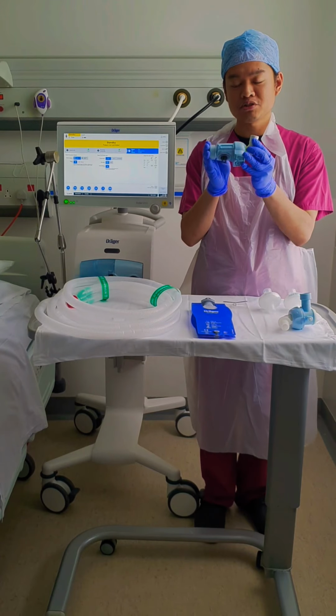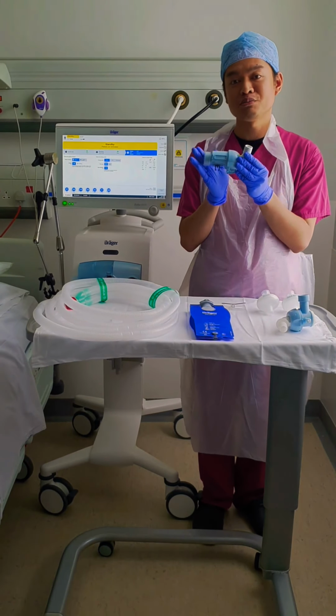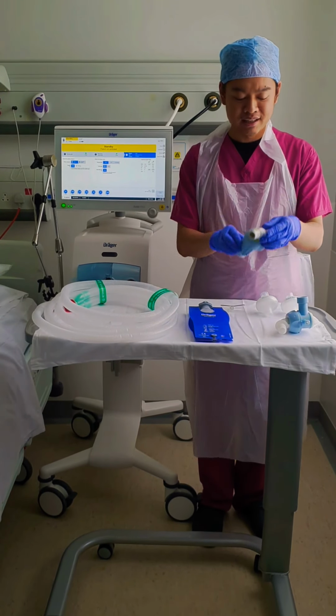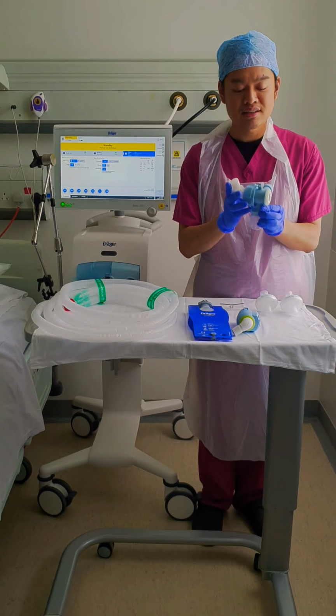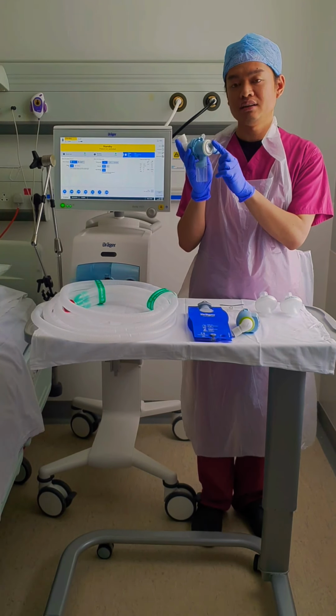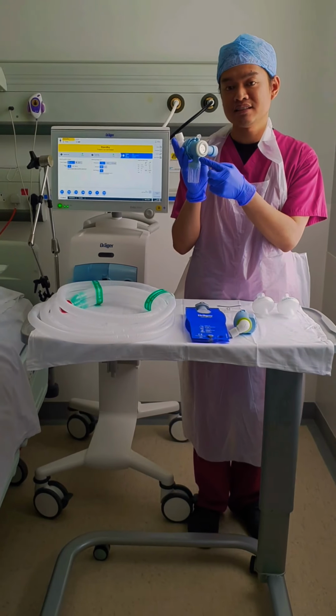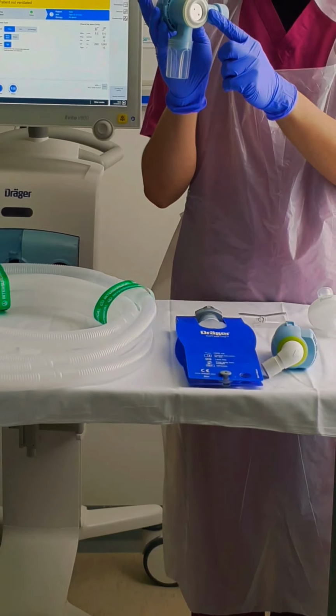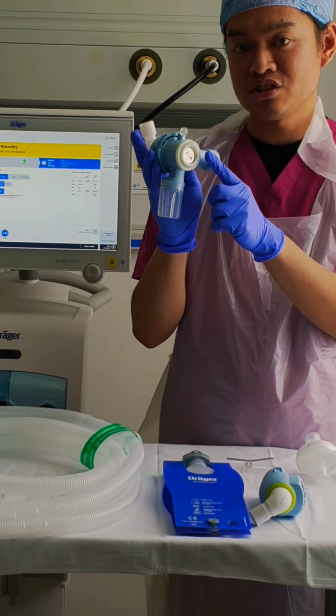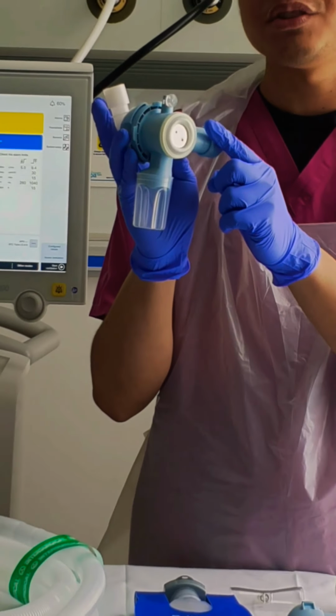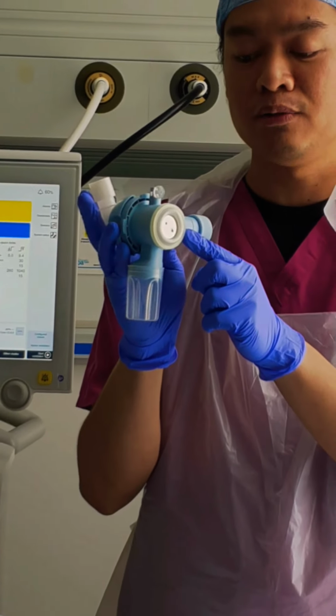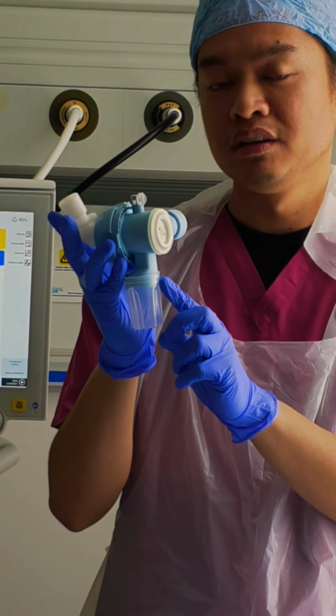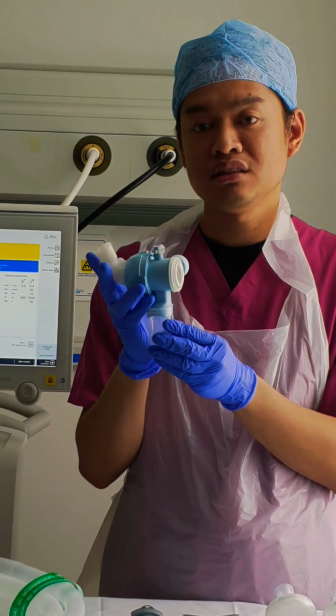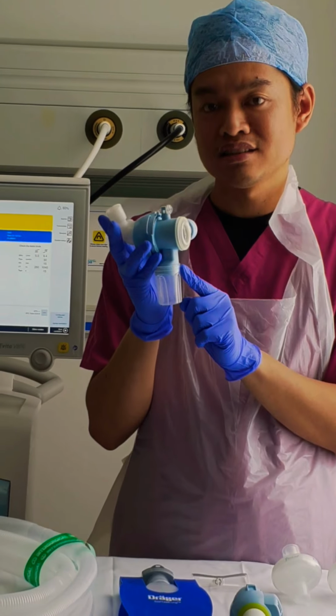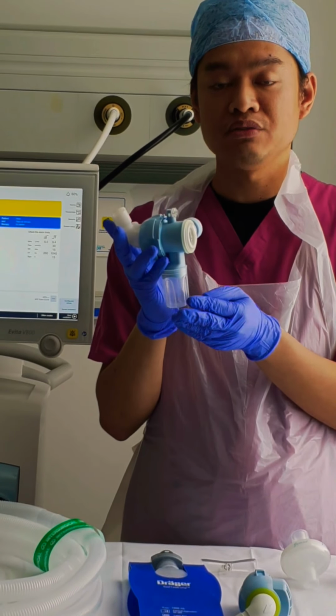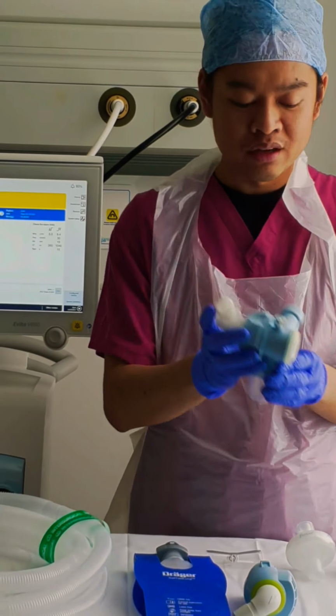The inspiratory port goes into the machine at an angle, which I'm going to be showing you in a minute. Next is the expiratory valve. I just want to point out that this is a diaphragm, and you have to make sure that this is actually attached to the expiratory valve. Otherwise your ventilator's SST will fail, and it has a water trap at the bottom. As per the company's recommendation, this can be used up to 7 days, or if there are shortages, obviously this can stay a little longer.